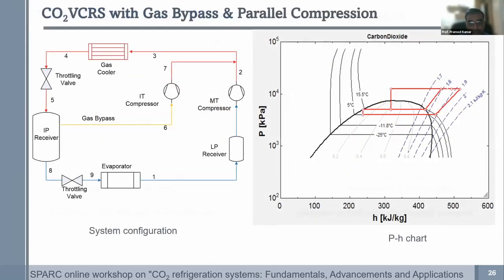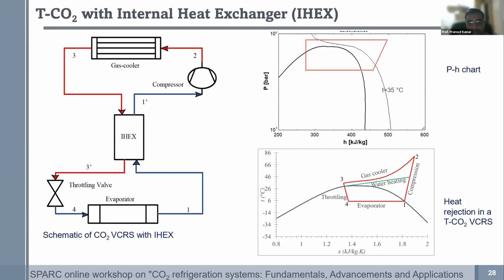Let me come to what I was talking about in terms of heat transfer in the supercritical phase. Of course, the water is going to undergo single phase heat transfer because you're below 100 degrees Celsius. But then you have to minimize this large delta T so that you can reduce the exergetic losses and hug this isotherm as closely as possible to ensure efficient heat transfer. So sizing and selection of the heat exchanger is very important.